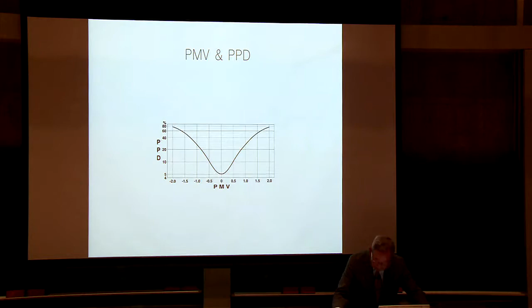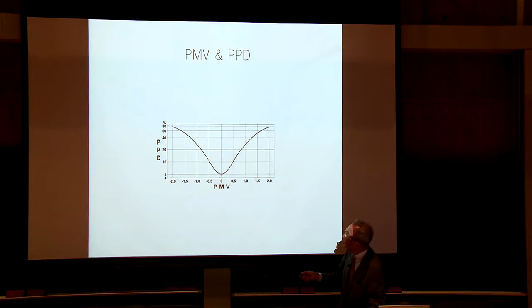Usually, the MET in an office building is 1.2, and CLO in summer is 0.5, and in winter, 1.0. If PMV falls between minus 0.5 and plus 0.5, it is supposed to be comfortable by ISO 7730. Still, 10% of people feel that the environment is unpleasant. PMV research was done by Professor Fanger, Technical University of Denmark. This is comfortable, but 10% of people feel dissatisfied.